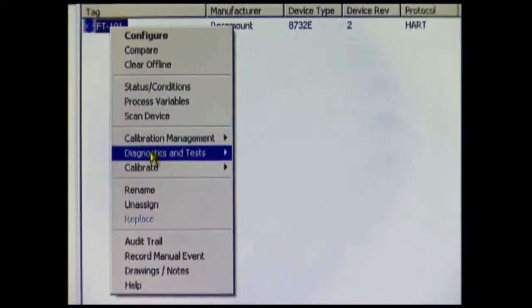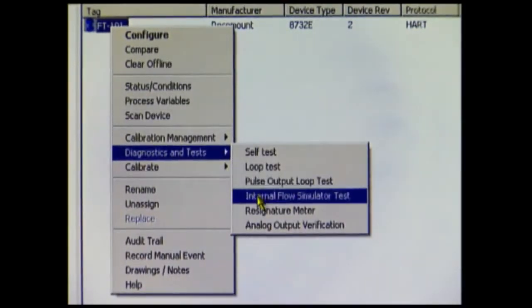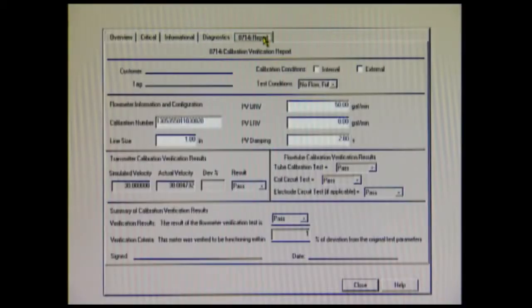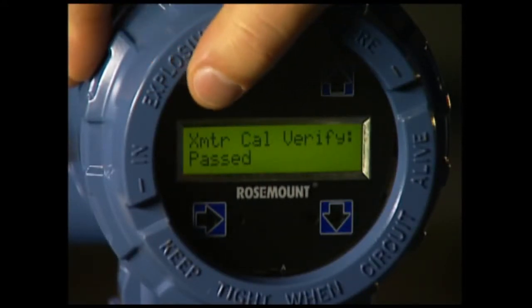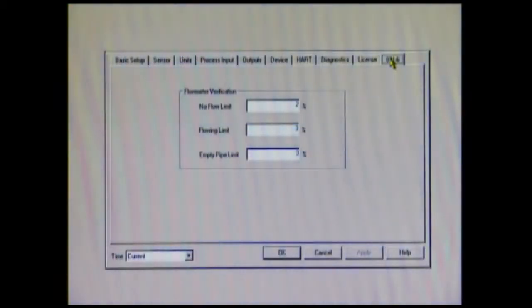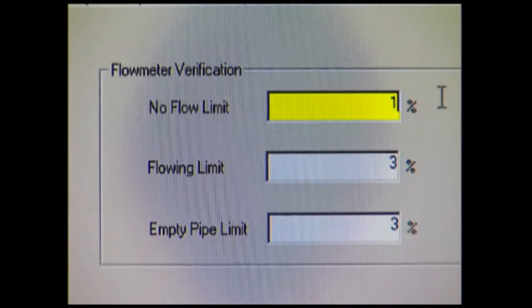With the 8714I diagnostic, you get a simple and straightforward method for running the verification that provides documented pass-fail results from the test, including quantified calibration deviation values for both the transmitter and the flow tube sensor. It's all tested to the pass-fail criteria you set for the application and conditions.